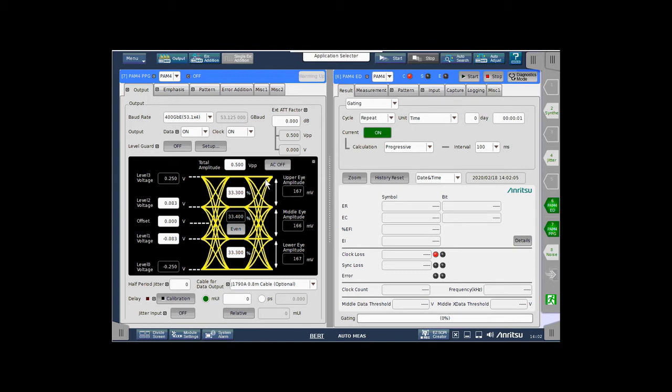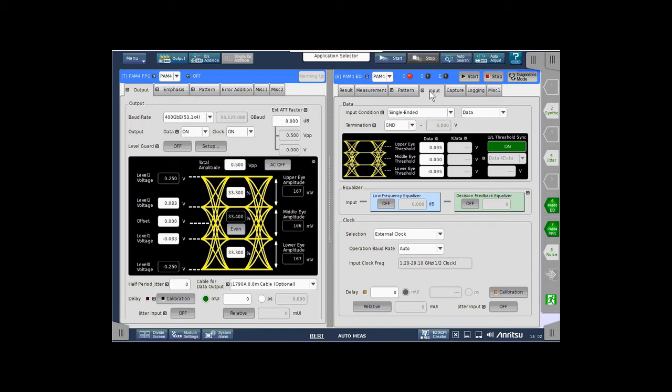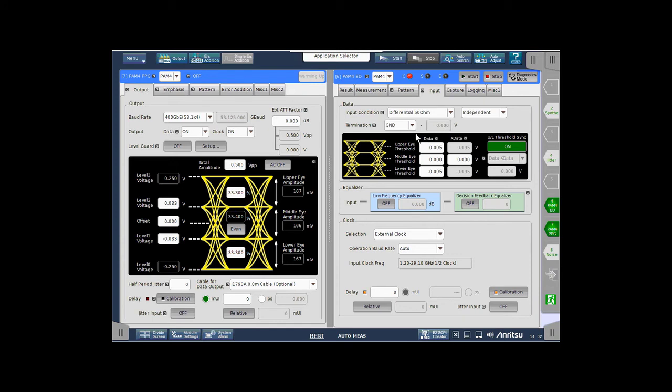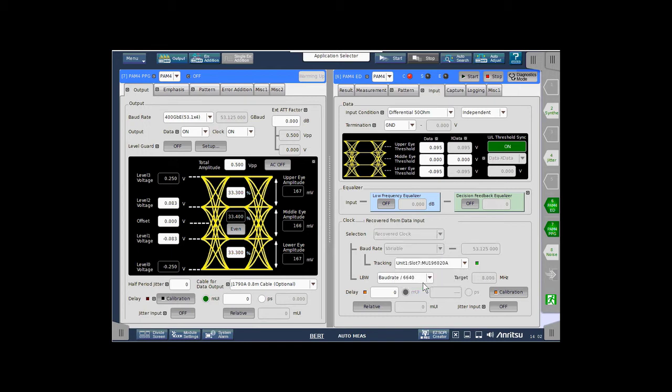Okay, on the error detector side, we are going to do a few things. I just want to change this to an untimed acquisition. And on the input tab, I am going to set the input condition to differential 50 ohms and also set up the clock recovery function for the error detector and tell the error detector that I would like the clock recovery set frequency to track the pattern generator rate setting.